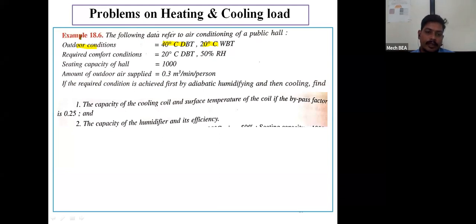The required comfort conditions are 20 degree centigrade dry bulb temperature and 50% relative humidity. The sitting capacity of that public hall is 1000 persons, and the amount of outdoor air supplied to the air handling unit is 0.3 meter cube per minute per person.